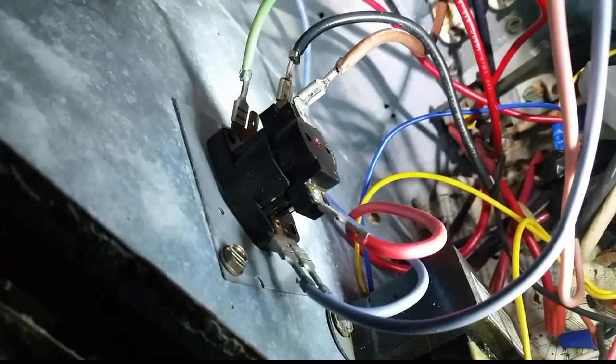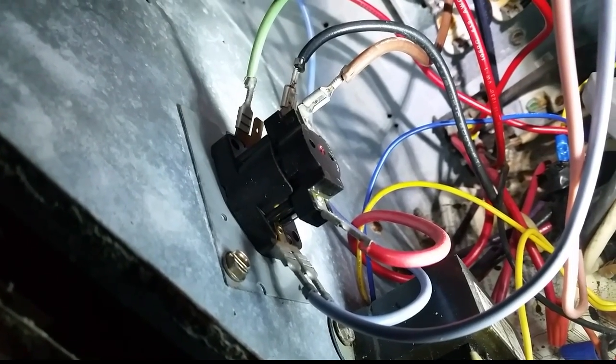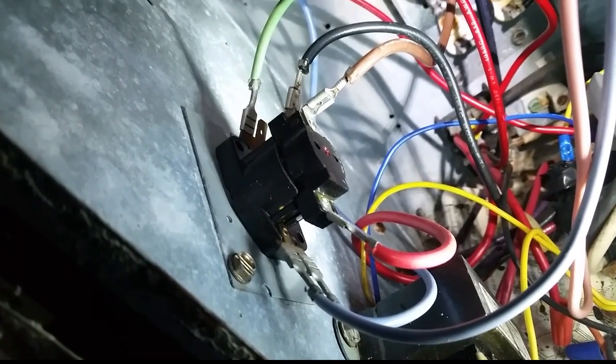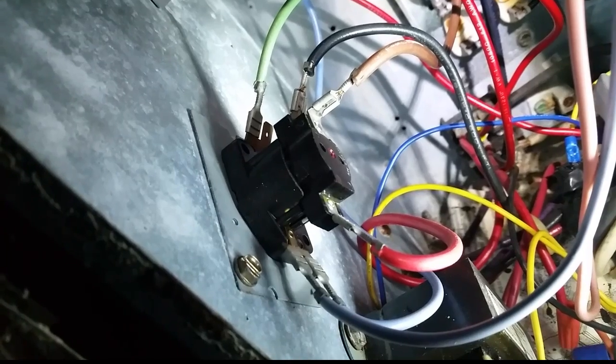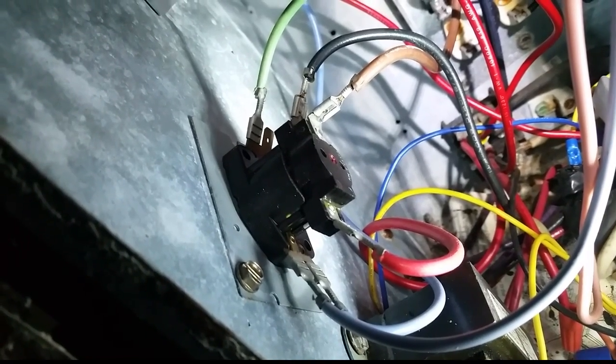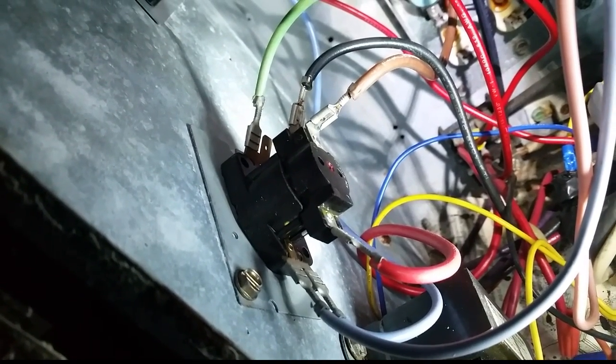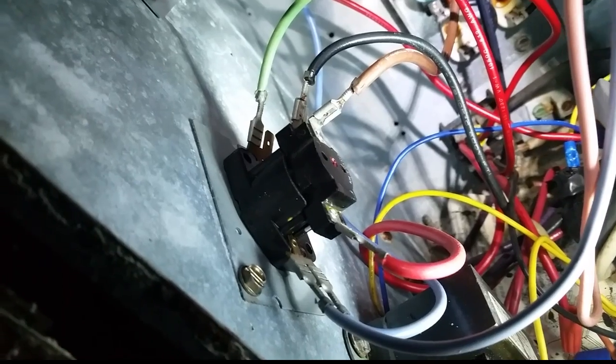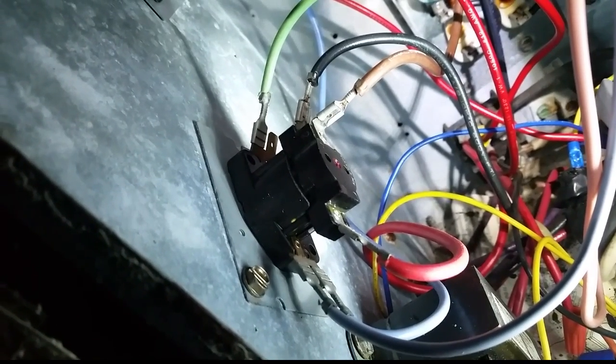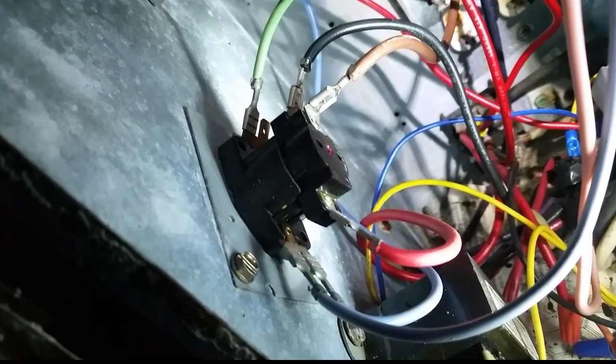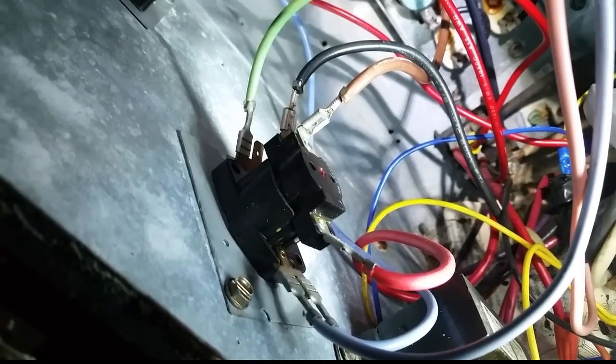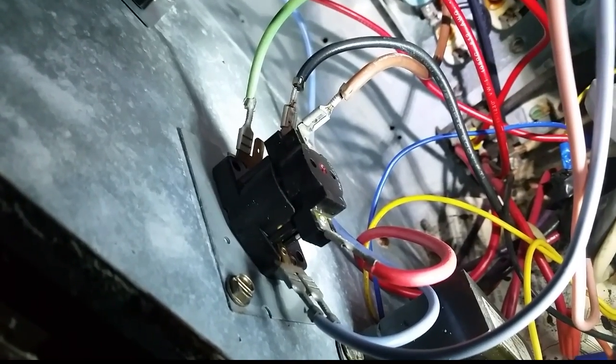One of the reasons people used to use these is because there's a delay just like on a regular sequencer that'll get your coil cold in the wintertime or coil cold in the summertime or hot in the wintertime and gives you a little bit of delay off to purge the ductwork. One of the main problems they don't use this is because it is unreliable and would break often.